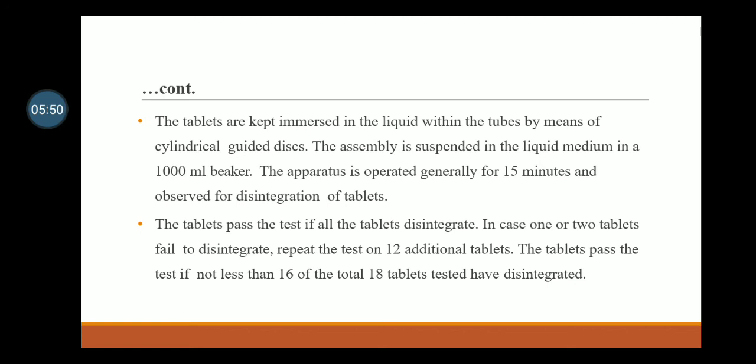The tablet passes the test if all the tablets disintegrate. In case one or two tablets fail to disintegrate, repeat the test on 12 additional tablets. The tablets pass the test if not less than 16 of the total 18 tablets tested have disintegrated.